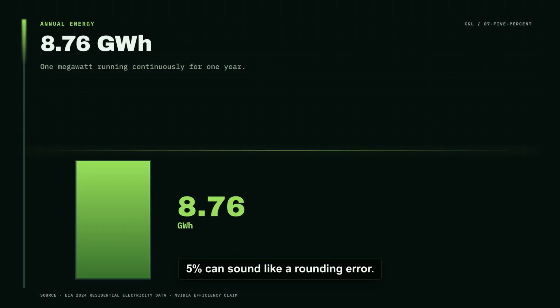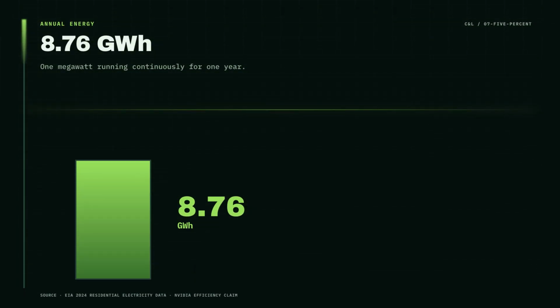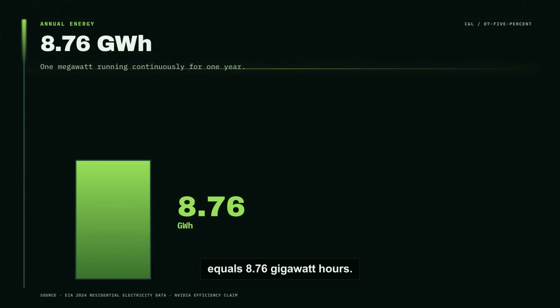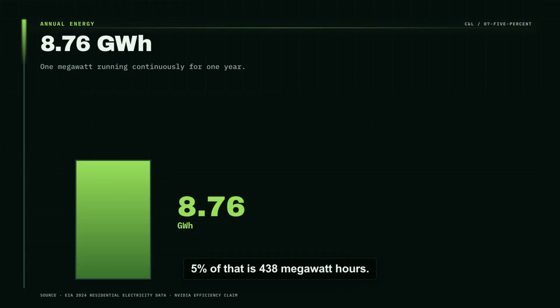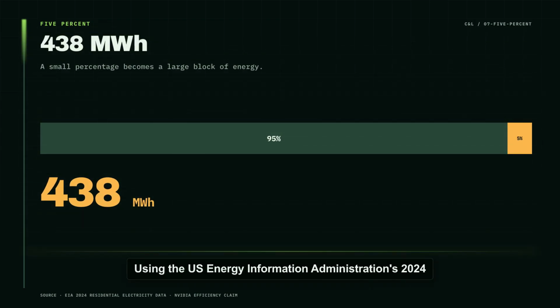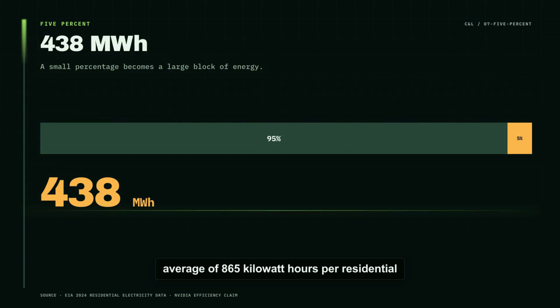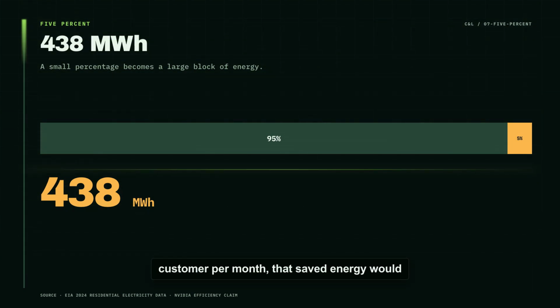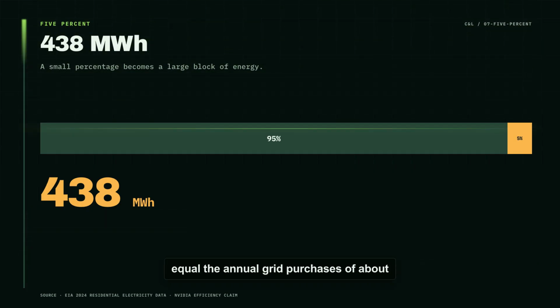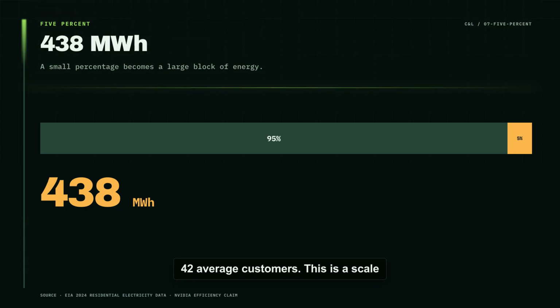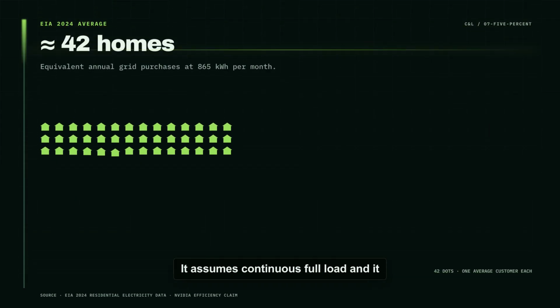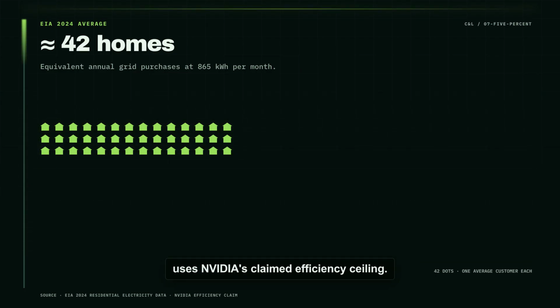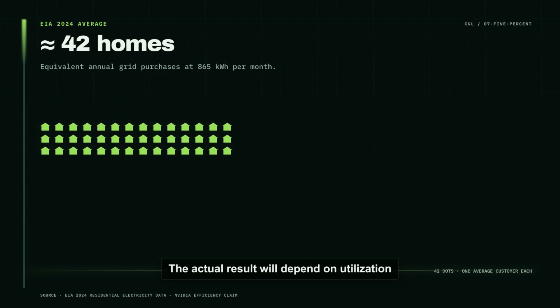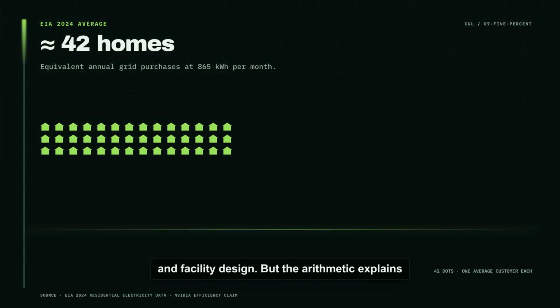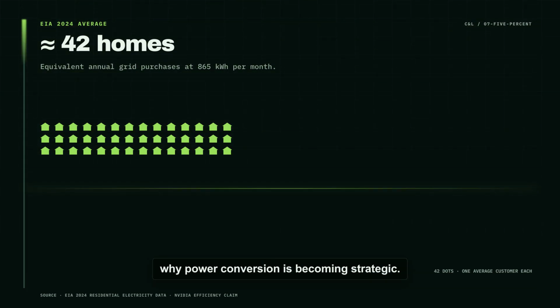5% can sound like a rounding error. At megawatt scale, it is not. 1 megawatt running continuously for a year equals 8.76 gigawatt hours. 5% of that is 438 megawatt hours. Using the U.S. Energy Information Administration's 2024 average of 865 kilowatt hours per residential customer per month, that saved energy would equal the annual grid purchases of about 42 average customers. This is a scale comparison, not a forecast. It assumes continuous full load, and it uses NVIDIA's claimed efficiency ceiling. The actual result will depend on utilization and facility design, but the arithmetic explains why power conversion is becoming strategic.